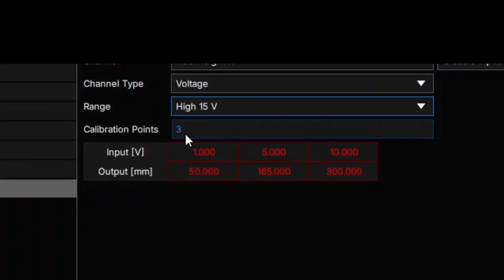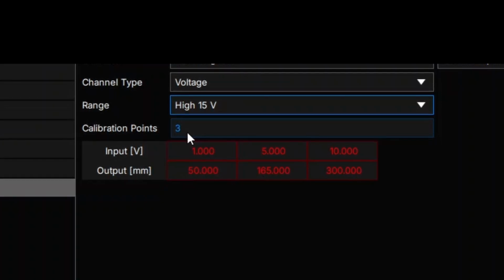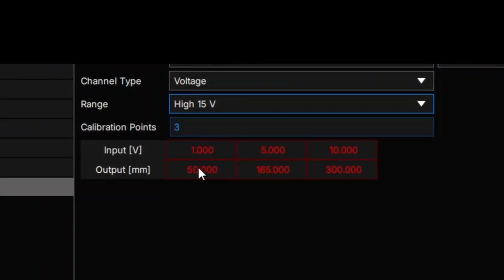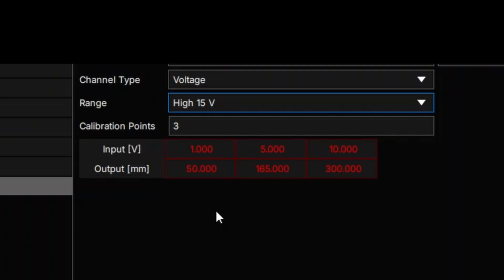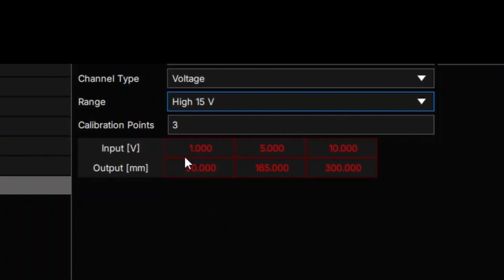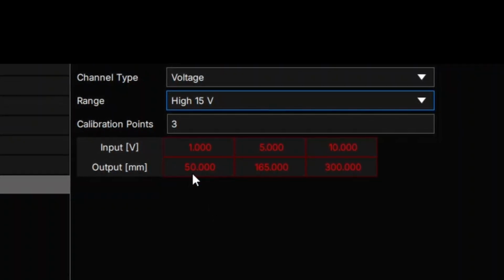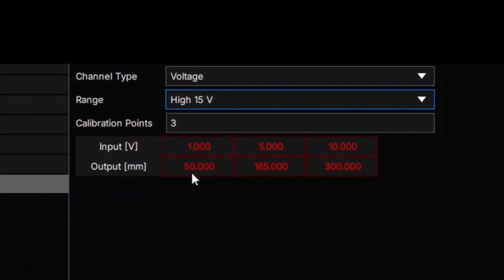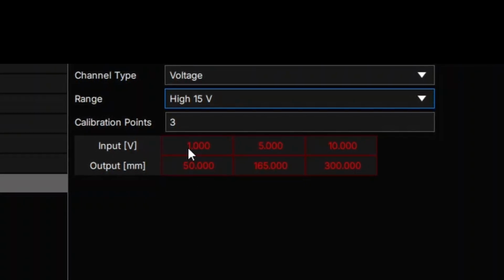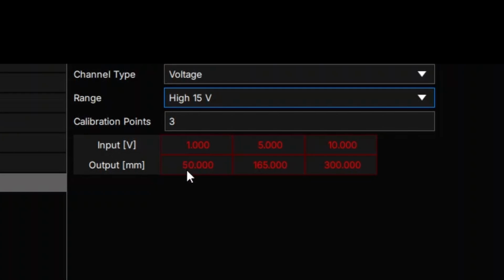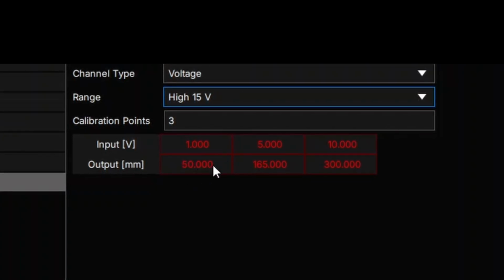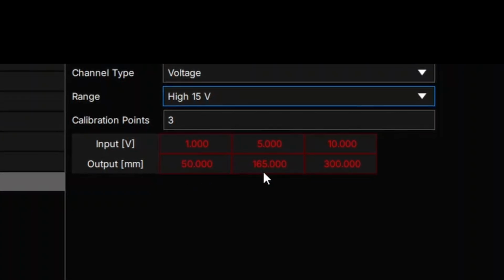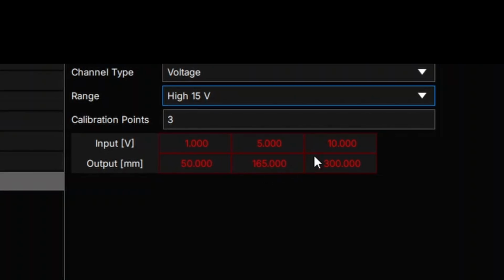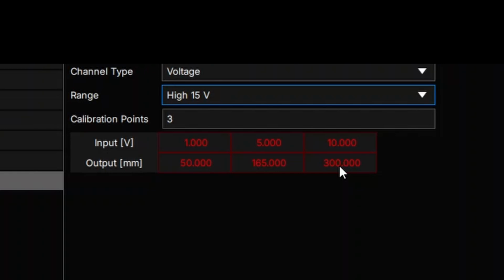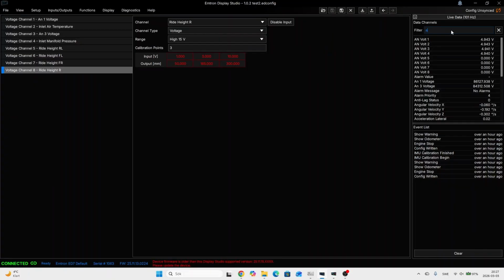And then I've set a calibration point, and I just chose 3. The sensor gives out a 1 volt signal at 50 millimeters, 5 volts at 165 millimeters, and 10 volts at 300 millimeters, and that's the range of the sensor.